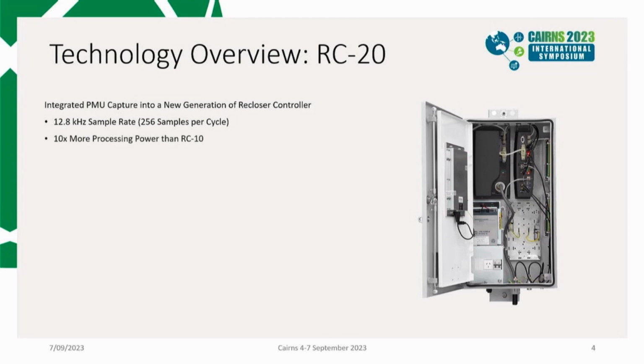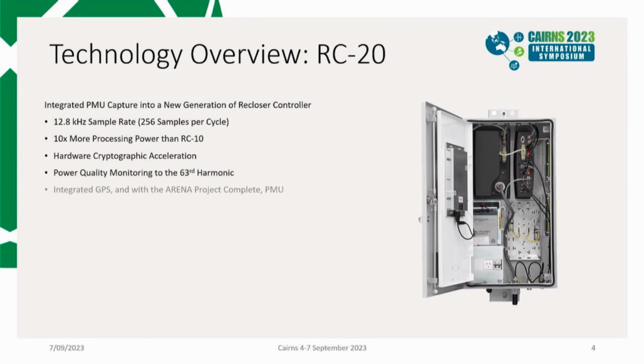So we boosted our sample rate up to 12.8 kilohertz from the existing 32 samples per cycle in the legacy products that are in service today, and implemented 10 times the processing power that we saw in the prior generation product. And that was to handle the high level of data input that was required, or data throughput, as the PMUs were generated around the network. This also allowed us to increase the power quality monitoring up to the 63rd harmonic, which was also of interest to network service providers, as the intention was to connect more renewable energy to the distribution grid.